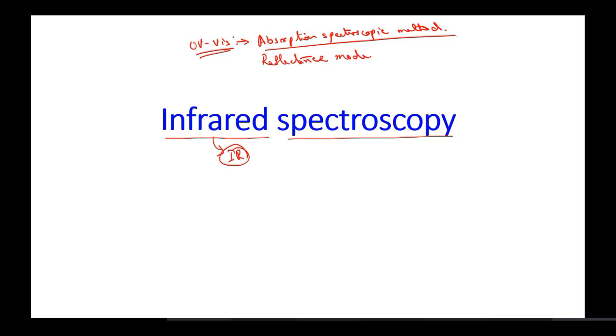As with UV-visible spectroscopy, where we could use it in the absorption mode or the reflectance mode, similarly in infrared spectroscopy also, we can have attachments such that the IR spectroscope can work in the absorption mode or the reflectance mode. Since it is an absorption spectroscopy, the basic instrumental functions remain the same. However, there is a slight change in the mechanism — how the peaks are being detected.